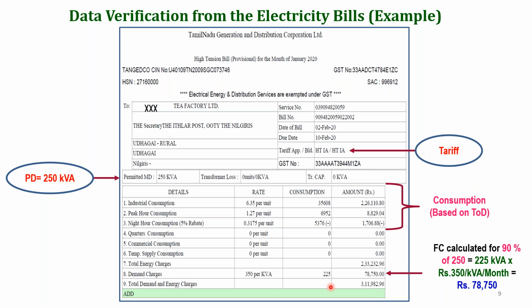For the calculation of the demand charge in Tamil Nadu, especially TANGEDCO is using a simple formula: 90% of the permitted demand or sanctioned demand, multiplied by 350 rupees per kVA per month. So 90% of 250 is 225. 225 multiplied by 350 is 78,750, which is the fixed charge. So this is represented here.